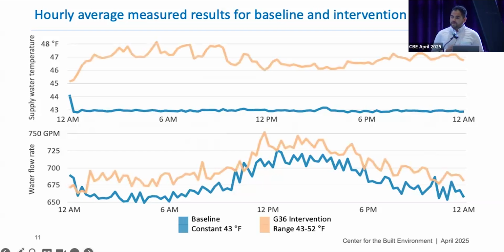In this case, we observed an average increase in the water temperature of 3 to 5 degrees Fahrenheit. And recall that the top of the range was 52, and we saw that it never got to 52 because the heat exchanger that serves the process cooling loads for the nanofab couldn't maintain their set point of 65 if we go with chilled water temperatures higher than 48 or 49. So the trim and respond block was finding an optimal temperature that was able to satisfy all the cooling loads.